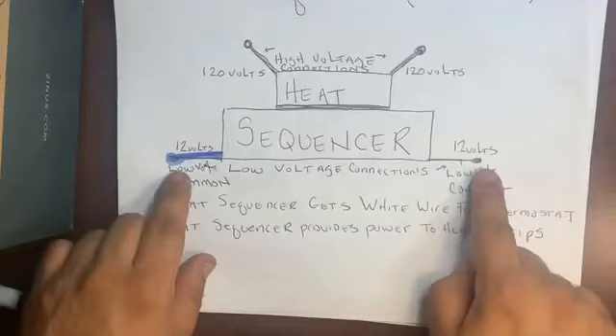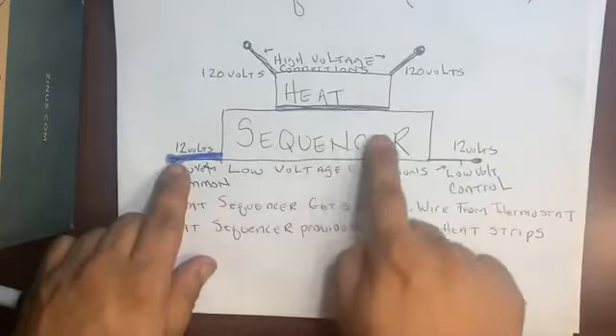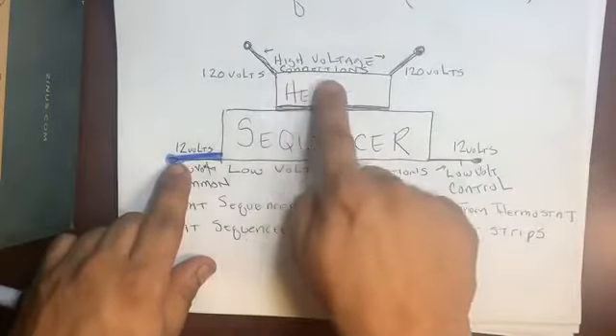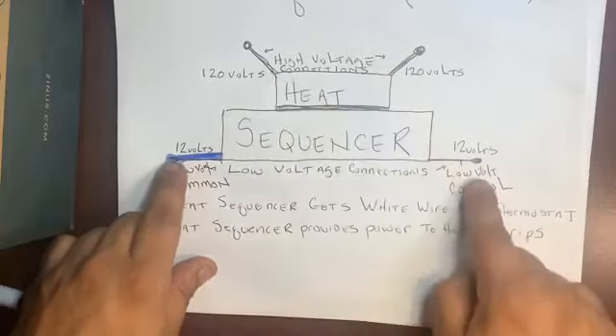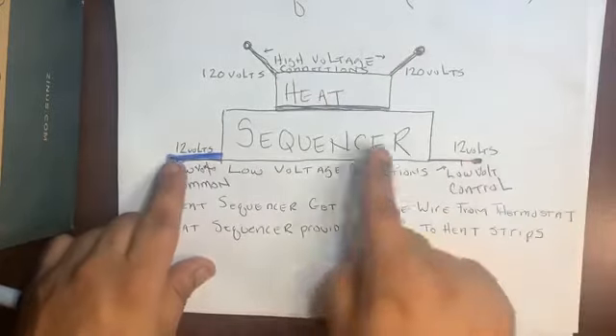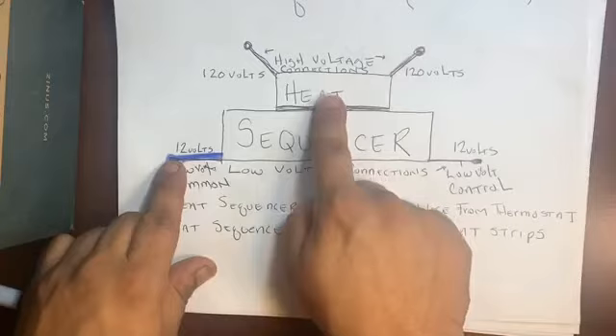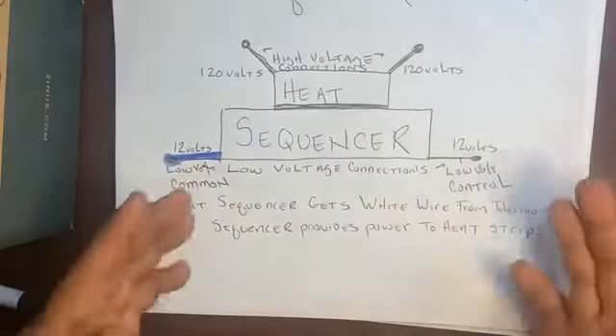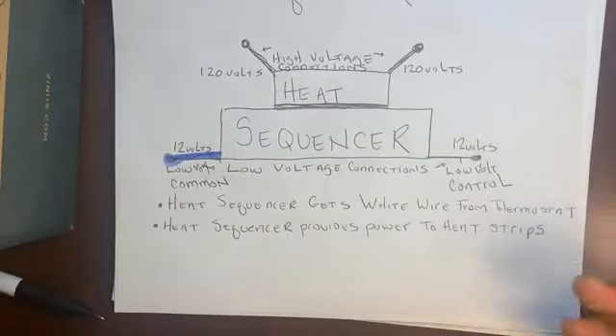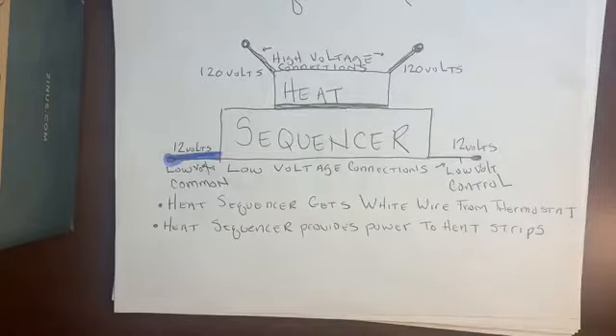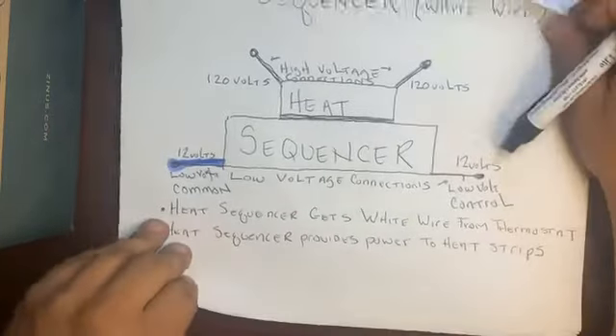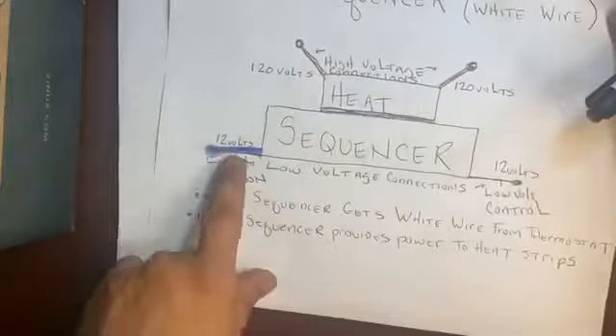This little metal, once it gets 24 volts on each leg, this bimetal will float up and then connect these two connections. Same thing, when the voltage is taken away by the thermostat, that bimetal will take a few seconds to float down. The reason we do that is we want to sometimes delay something turning on or off. But this is our first relay, our heat sequencer. 12 volt common. Common, common, common.